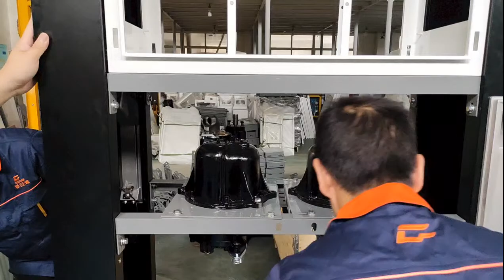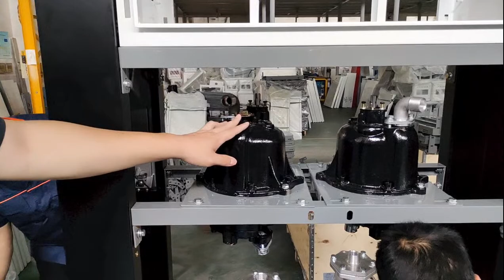If you turn too much, it will damage it directly. This is for calibration. If the filling is not accurate, we can make the calibration here. So this is for the mechanical type's calibration. We have a controller that can do it too, but the controller isn't ready yet.